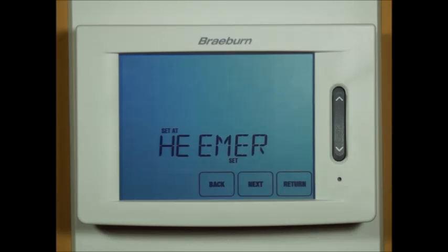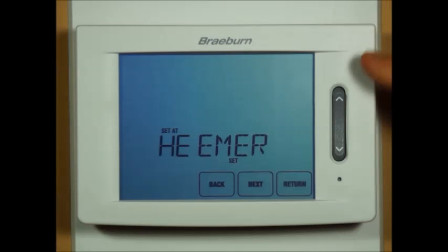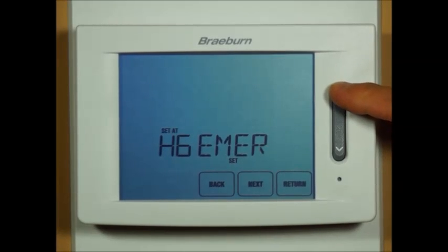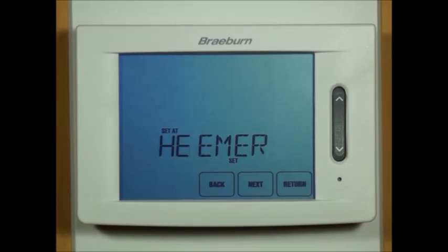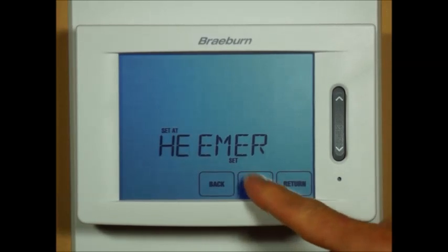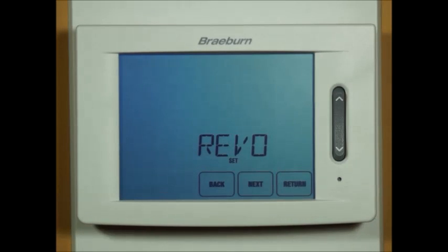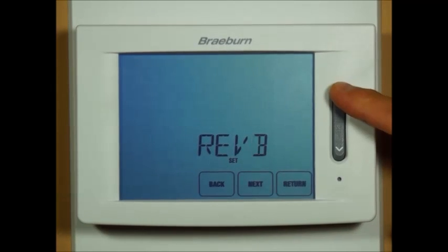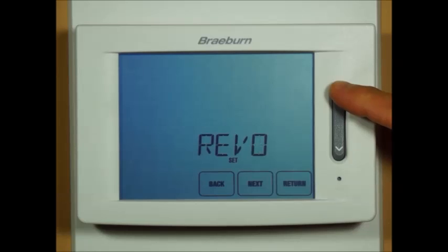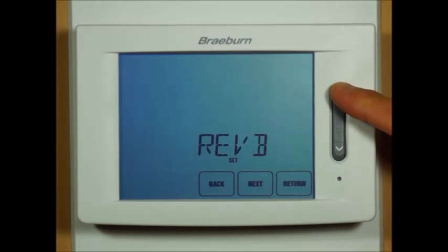Heat electric for emergency — that's asking what type of emergency heat you have on this heat pump: electric emergency heat or gas emergency heat. Reversing valve O or reversing valve B: O is for a cool active reversing valve, and B is for a heat active reversing valve.